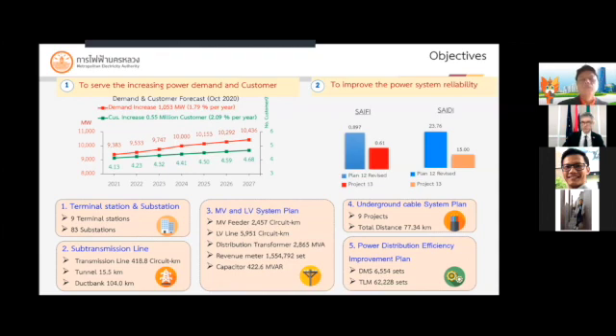sub-transmission line system plan for building new lines and improving existing sub-transmission lines when a new power station is formed or there is a change in the power distribution scheme. Number 3, medium and low voltage system plan. Number 4, underground cable system plan. And number 5, the last one, power distribution efficiency improvement plan. For example, installing a DMS, distribution management system, or TLM, transformer load monitoring system, that will help improve the stability of the electrical system.